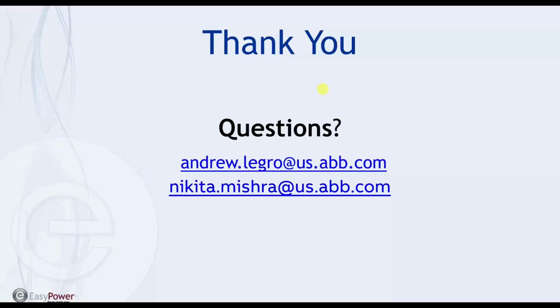Right. And then the last question, are MV breakers typically 100% rated? Yes. The ratings are completely different than low voltage, but yeah, they're 100% rated, with the caveat that for your particular application in terms of temperatures and whatnot, you may want to go in and look at that to make sure that you're within that rating.